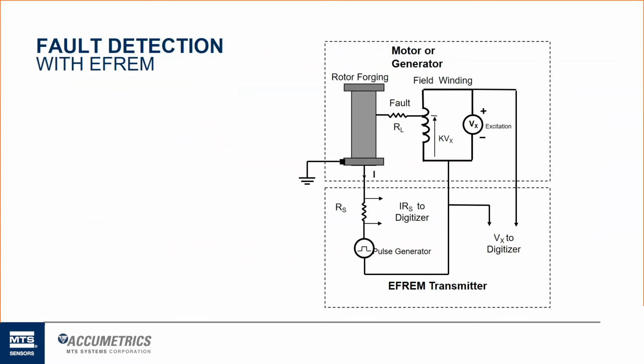So here's a little bit of an example. What's different from the EFREM system versus the classical method is that instead of injecting just a set DC voltage, we inject a pulse that's toggled from high to low. We also connect to the positive side of the excitation field and the negative side. As that pulse is toggled from high to low, we're doing high-speed digital, two simultaneous computations of the resistance value between the negative side of the field and rotor ground, and the positive side of the field and rotor ground, and transmitting that off of the shaft simultaneously.